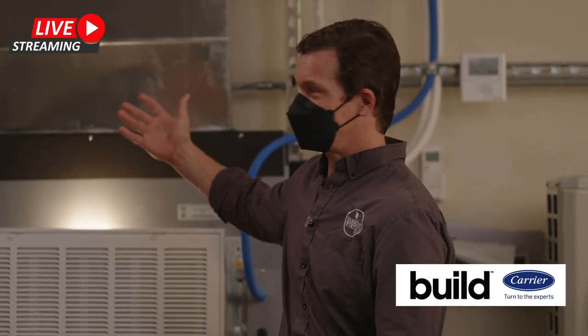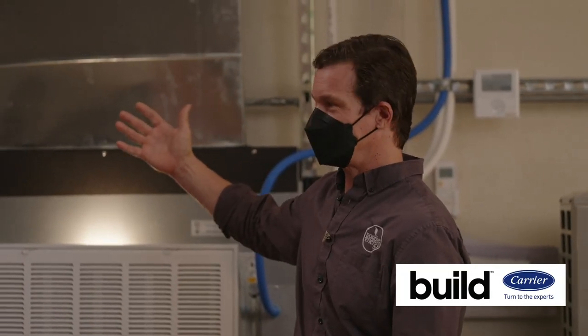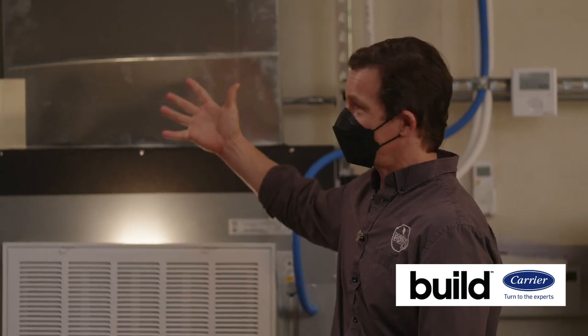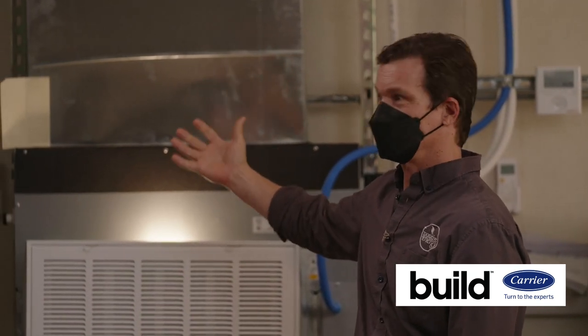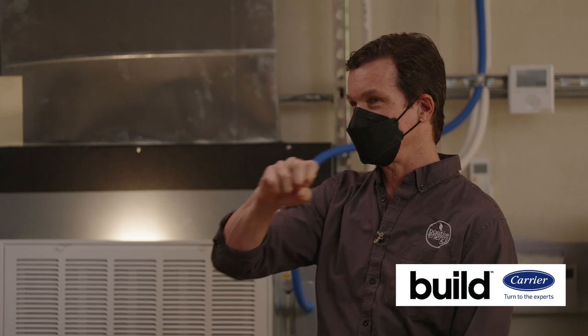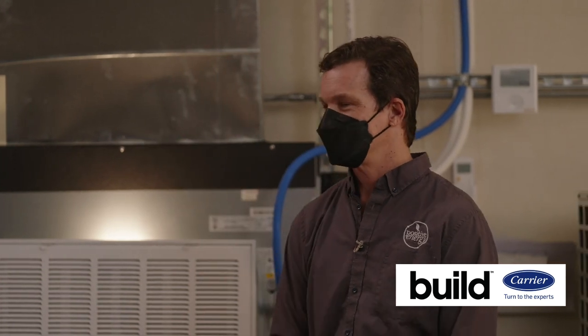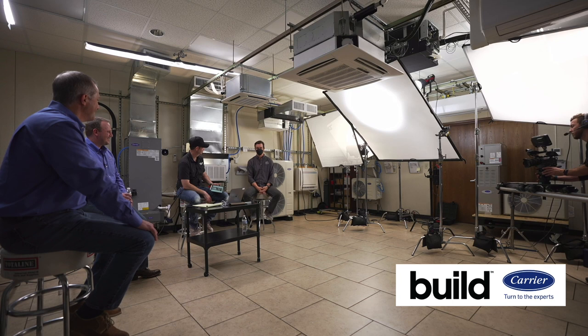That's right. I mean, your body's thermal experience of a space is dominated by the surface temperatures around you. This room is filled with about 1,000 pounds of air. So if that wall, say the west wall, is getting hot from western exposure, the air adjacent to it is going to cool it off. It's going to absorb the heat and take it back through the return, get cooled, and get ready to do it again. So we use air conditioning to make the wall cool, to make our client cool. It's kind of an interesting balance.